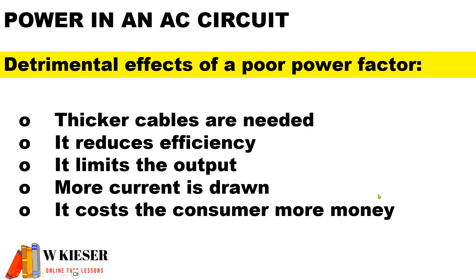What are the detrimental effects of a poor power factor? Thicker cables are needed to handle the larger current. It reduces efficiency, it limits the output. More current is drawn and it costs the consumer more money.